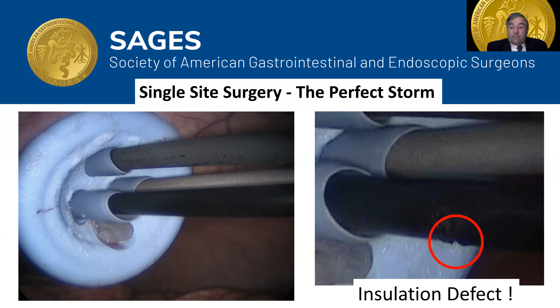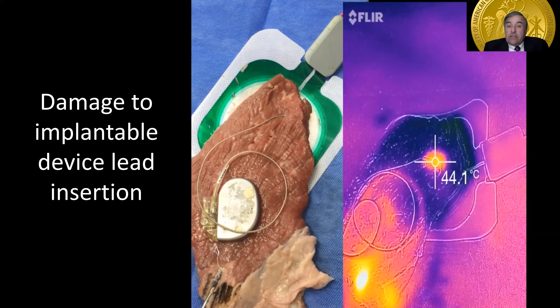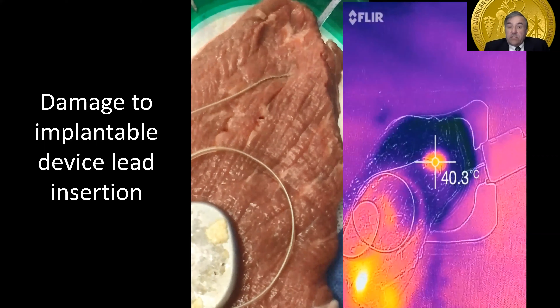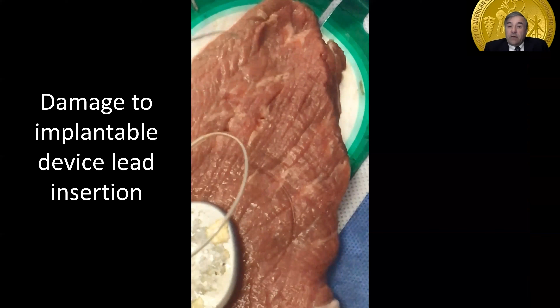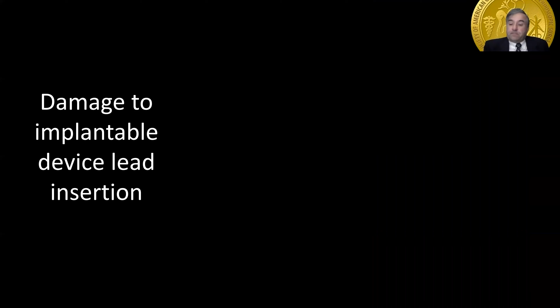Then there is the situation where you have an implantable device and you're operating in the vicinity with an electrosurgical instrument. This can happen. Now you can see there on the bottom, the instrument is activated, and what is shown here is that the tip of the lead from the implantable device, where the energy is most dense, heats up. Even though you don't necessarily see the burn happening with the naked eye, that lead gets very hot because of energy transferred through the device into the lead. And now you can see how that lead created a burn. Clearly, in a situation like that, the device becomes non-functional and has to be replaced.